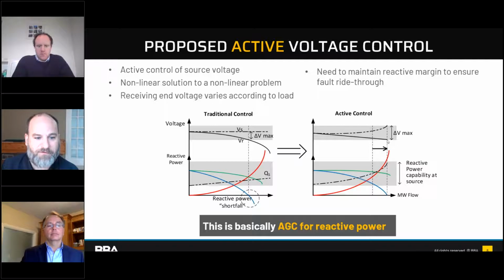This is when the trigger for voltage variation is not load, and this is key. Because what we're trying to do is keep the voltage set up so your on-load tap changers and cap banks are still there for you, when you need to control the system as it ramps up and down in the morning and evening.